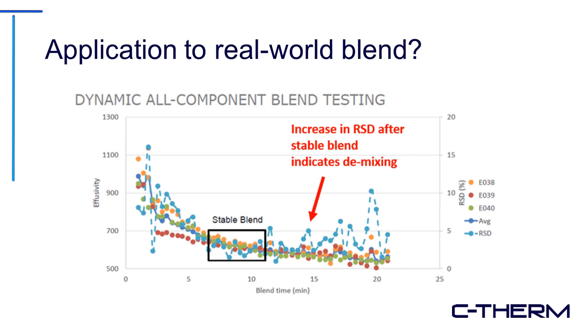This is a very quick example. We covered a bunch of other permutations of things that could cause it, including looking at spotting additives as they're added into a blend, those sorts of things. But this is just one plot from the paper that we wrote. You can see here we've got 4 different components, and we can identify, using the thermal effusivity, a region where the blend is stable, and then a region where the relative standard deviation starts getting spiky, and it spikes up in some cases above 10% relative standard deviation. Whereas in the stable blend region, it's typically less than about 3.5% in most cases.